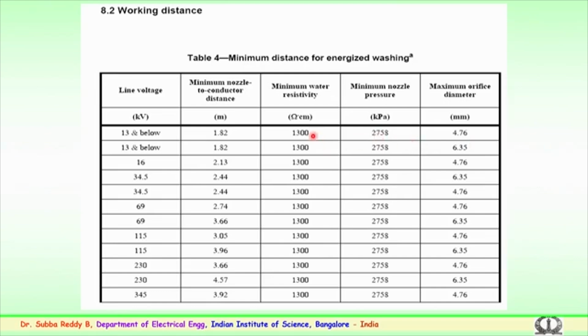So, here you can see most of the voltage levels as increases, the minimum nozzle to diameter of the conductor varies, but the minimum water resistivity is maintained same. You can see it is 1300 ohm centimeter in whatever voltage levels. Similarly, the minimum nozzle pressure, you can see it is not depending upon the voltage levels, it is maintained at a particular pressure as the insulators have to be cleaned. And maximum orifice diameter also changes as the voltage levels. You can see various type of nozzles of diameters are being employed. So, this table gives an important information.